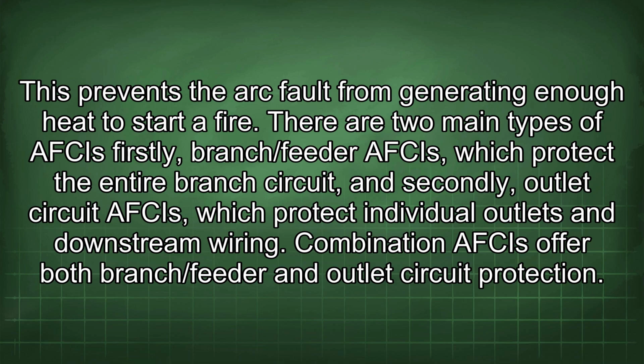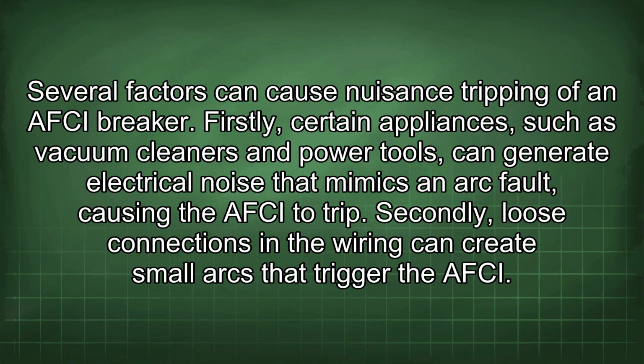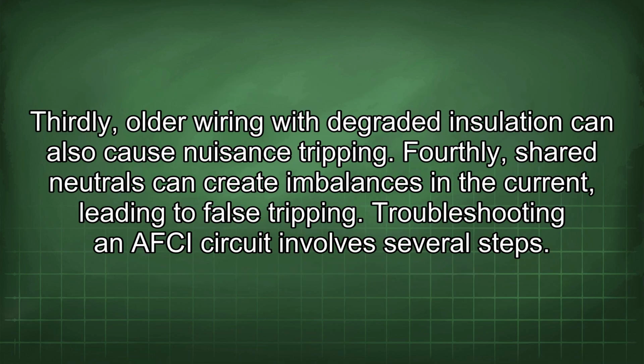There are two main types of AFCIs. Firstly, branch/feeder AFCIs, which protect the entire branch circuit, and secondly, outlet circuit AFCIs, which protect individual outlets and downstream wiring. Combination AFCIs offer both branch/feeder and outlet circuit protection. Several factors can cause nuisance tripping of an AFCI breaker. Firstly, certain appliances, such as vacuum cleaners and power tools, can generate electrical noise that mimics an arc fault, causing the AFCI to trip. Secondly, loose connections in the wiring can create small arcs that trigger the AFCI. Thirdly, older wiring with degraded insulation can also cause nuisance tripping. Fourthly, shared neutrals can create imbalances in the current, leading to false tripping.